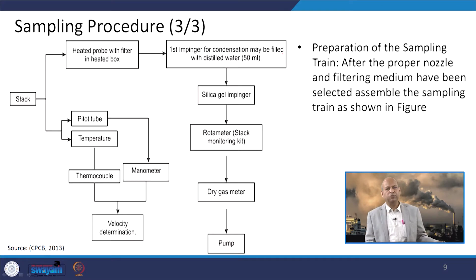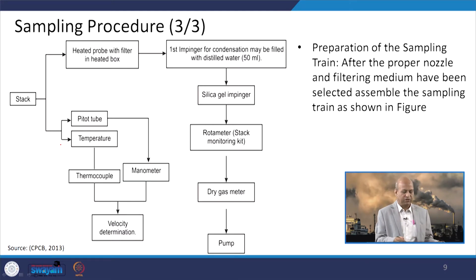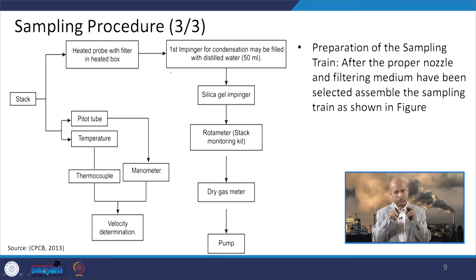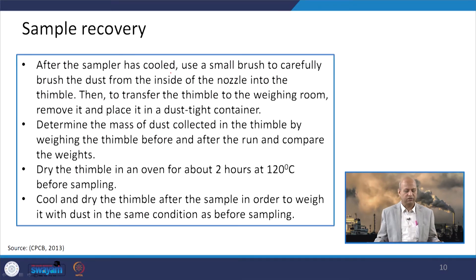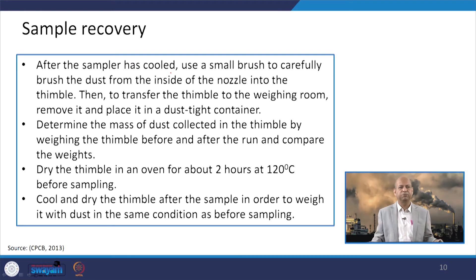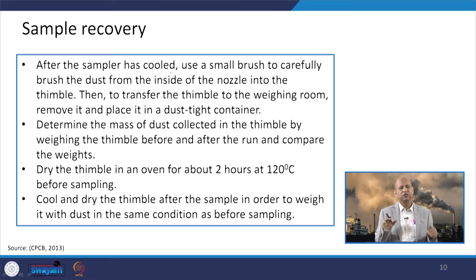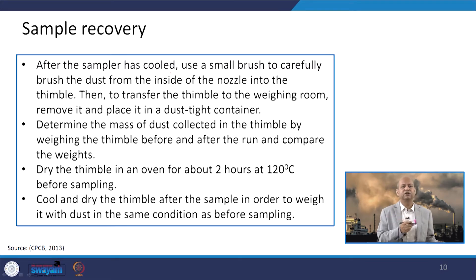Regarding the sampling procedure, there are two streams: one gives temperature and velocity-related values, and the other is where the particulate matter is collected. When sampling is complete, we collect the filter paper and must ensure there is no addition of particulate matter from outside. The mass of dust collected on the filter paper or thimble is weighed. It should be kept in an oven for about 2 hours at 120°C to remove any error due to moisture. The weight is taken before and after sampling, and the difference gives the concentration.